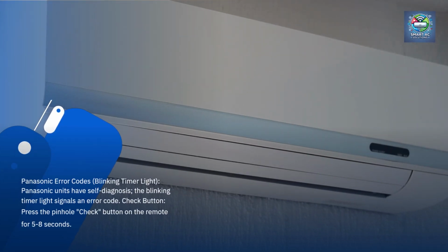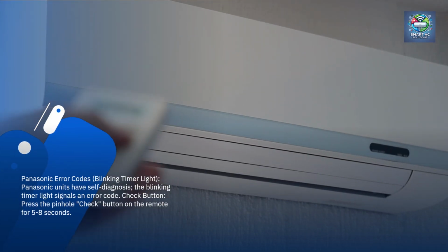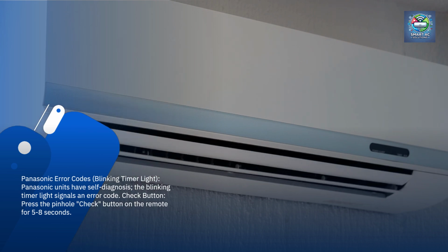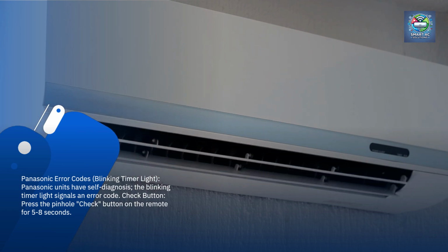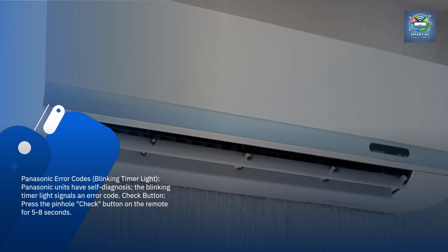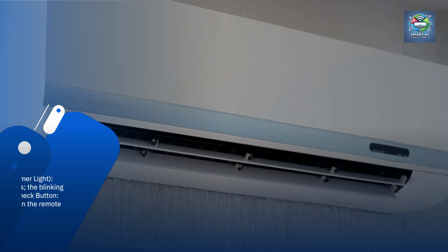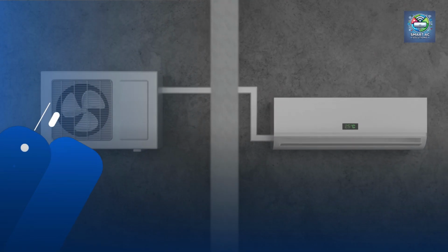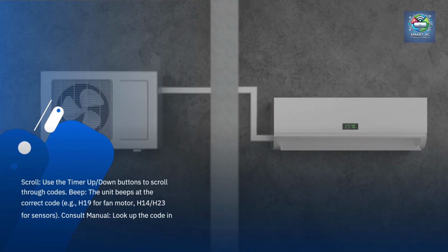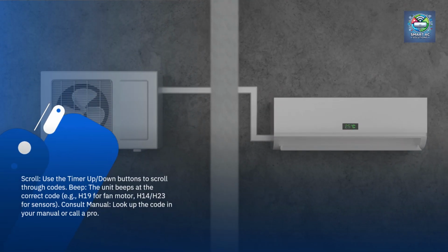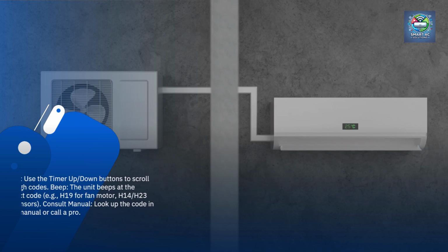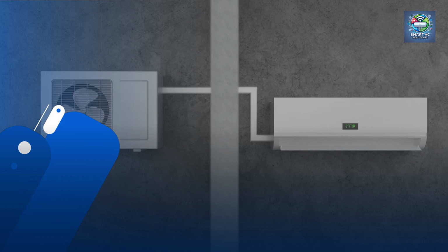Panasonic error codes, blinking timer light. Panasonic units have self-diagnosis. The blinking timer light signals an error code. Check button. Press the pinhole check button on the remote for 5 to 8 seconds. Scroll. Use the timer up, down buttons to scroll through codes. Beep. The unit beeps at the correct code, e.g., H19 for fan motor, H14, H23 for sensors. Consult manual. Look up the code in your manual or call a pro.